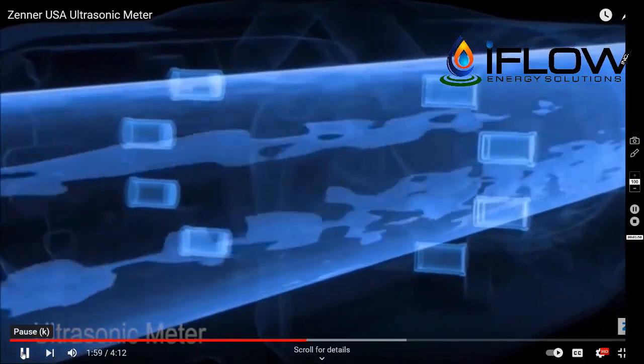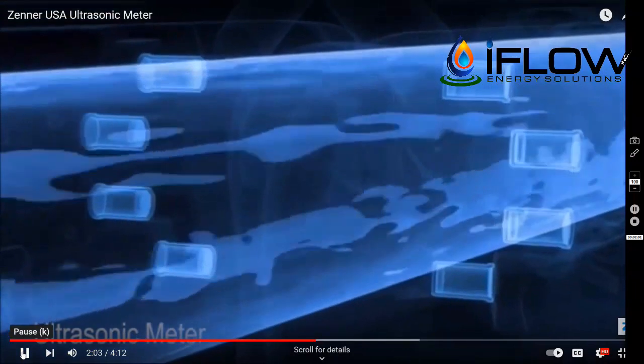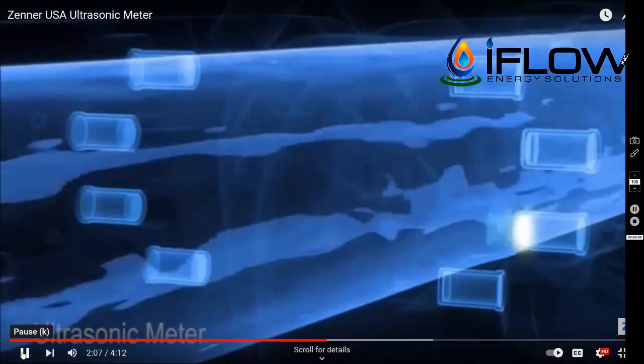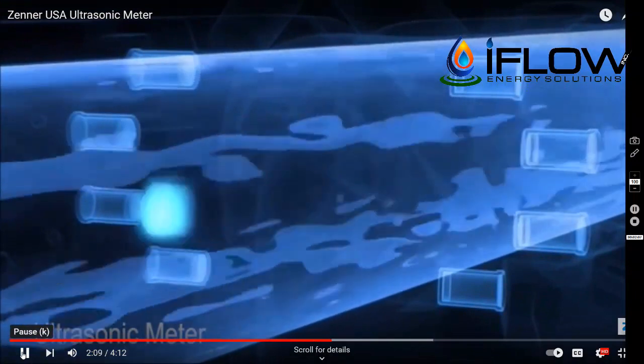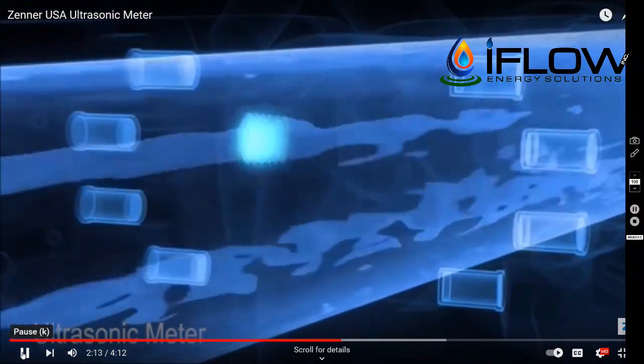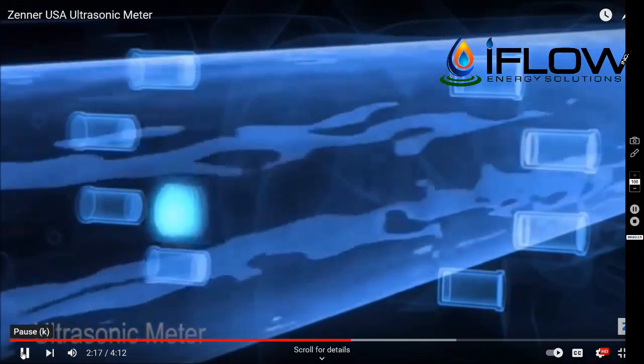Once the fluid starts to flow in the measuring tube, the ultrasonic signals are accelerated in the direction of the flow and decelerated against the flow. As a result, the ultrasonic signals now have different transit times, less time in the direction of flow and more time against the flow.